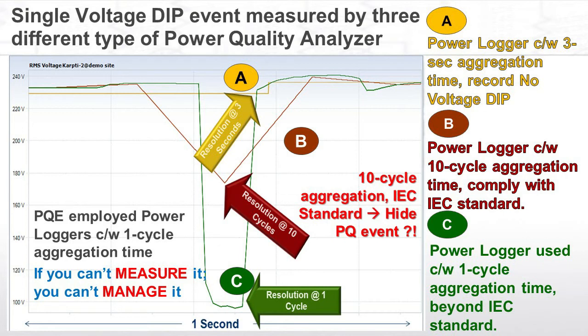Conclusion: Power quality analyzer C, having the finest aggregation time — that is, single-cycle aggregation time — measured a more accurate and correct voltage dip compared to analyzers with 10-cycle and 3-second aggregation times. This test result reminds us of the slogan: if you cannot measure it, you cannot manage it. Therefore, it is of utmost importance to use a single-cycle aggregation time power quality analyzer for detailed and accurate on-site voltage dip measurement.